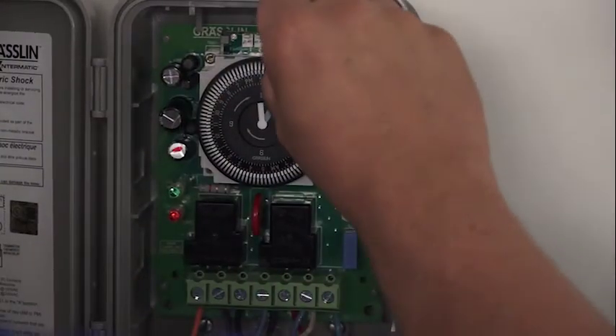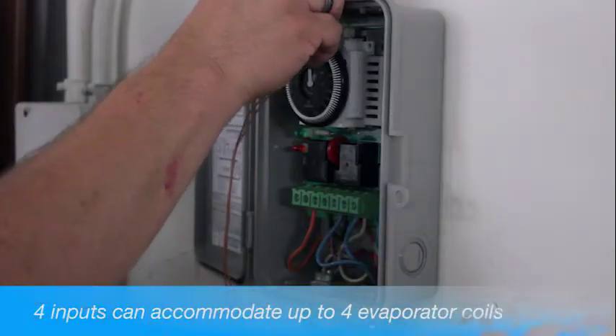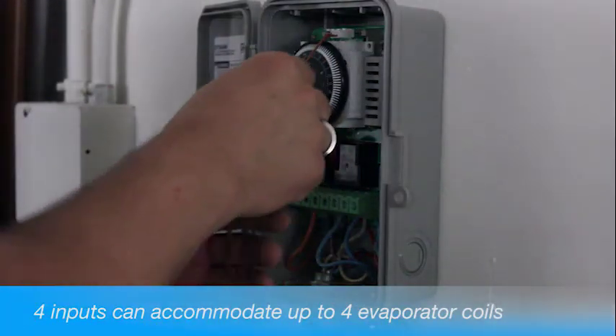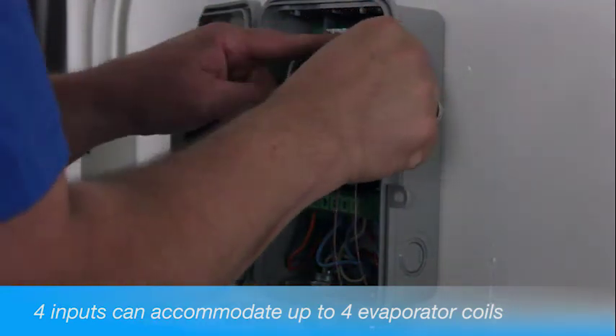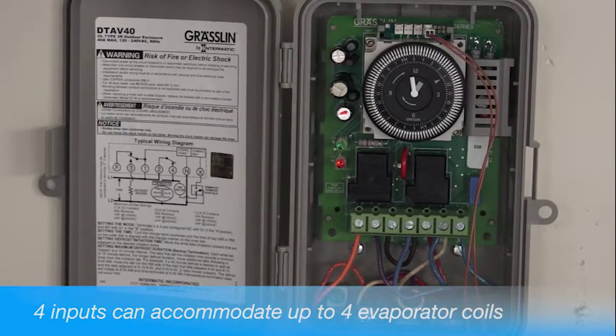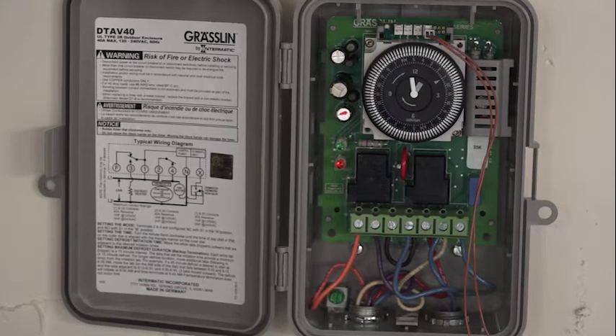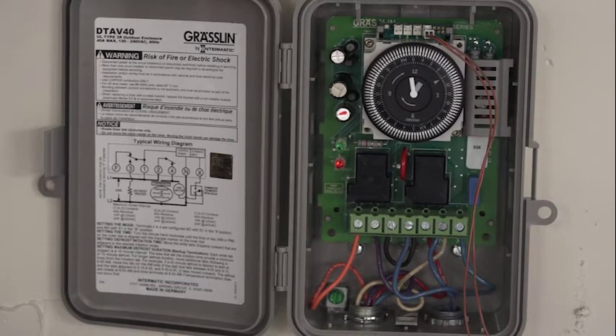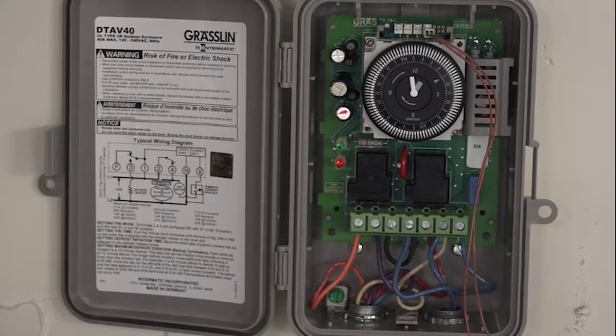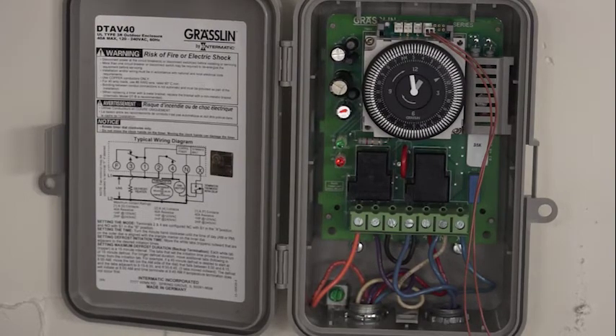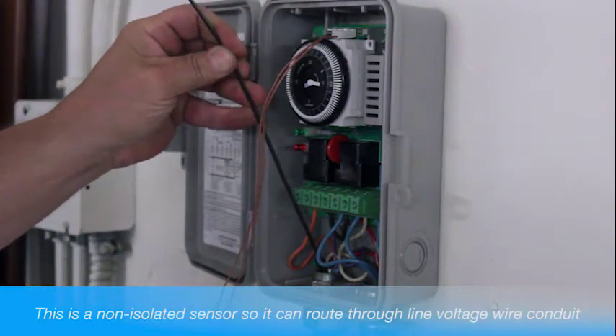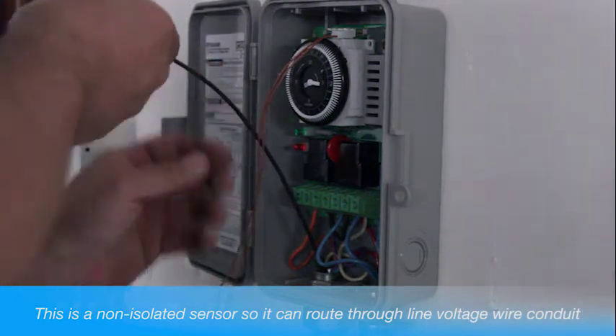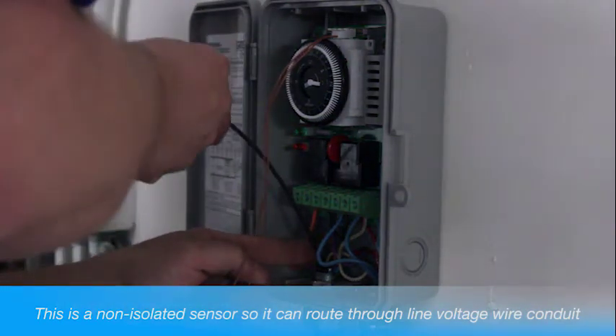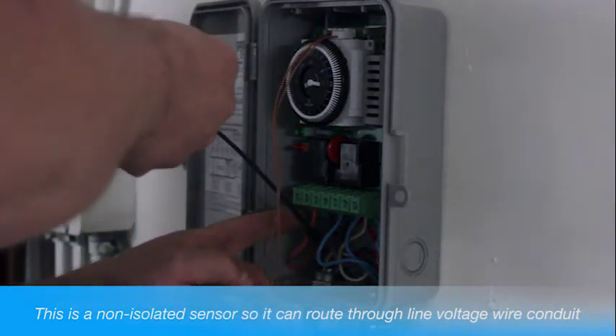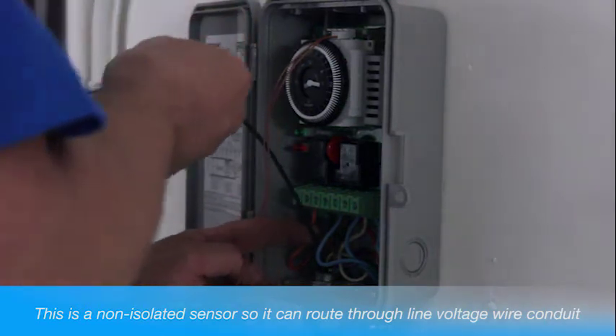Now, insert the input lead onto any of the 4 inputs on the Icube. 4 inputs on the Icube module accommodate up to 4 evaporator coils. Then, route the input lead above and around the module tab located on the right side of the module. Make sure the lead stays over the tab. For this installation, we're going to fish the thermistor probe leads through the existing conduit using fish tape. Note, sensor wire is expandable up to 400 feet using typical 18-gauge shielded or unshielded field wire.